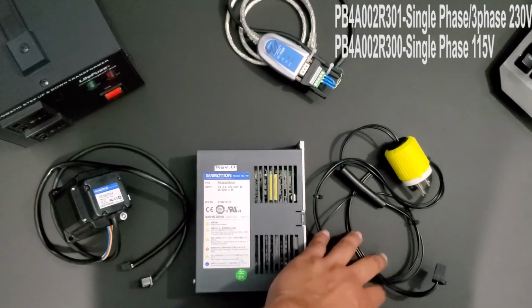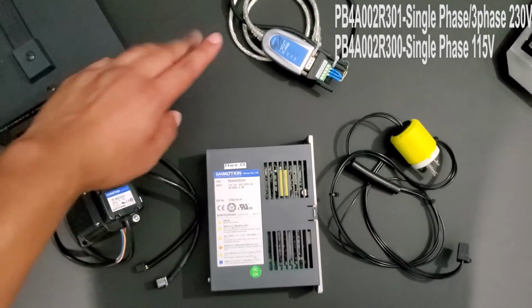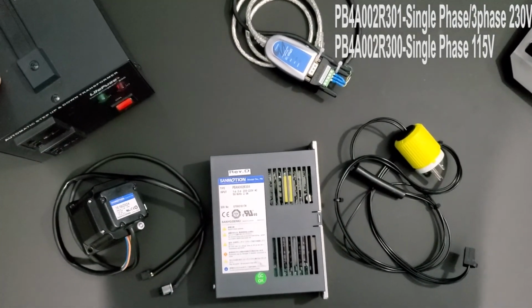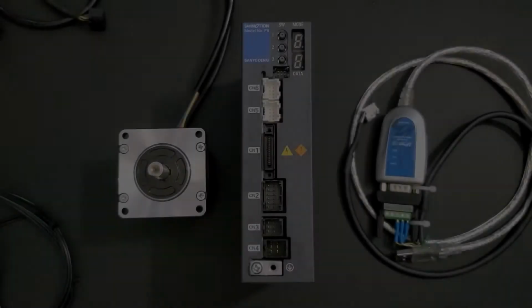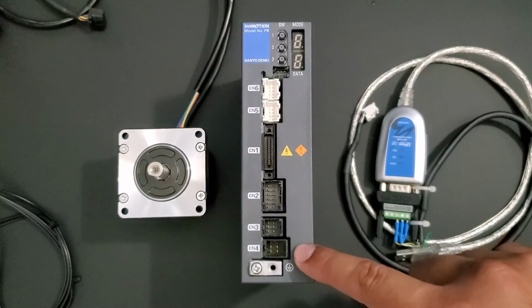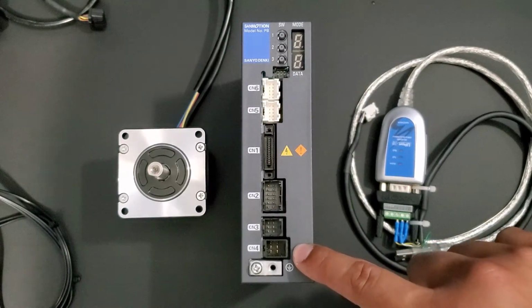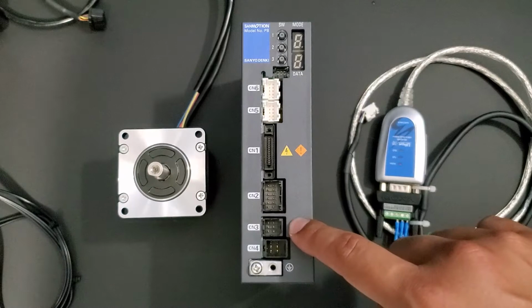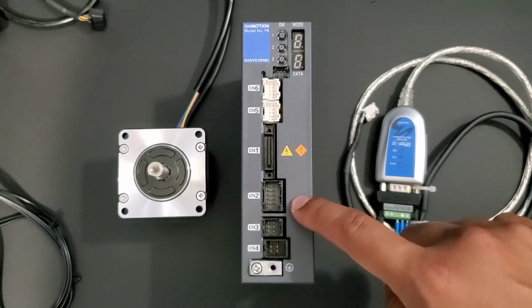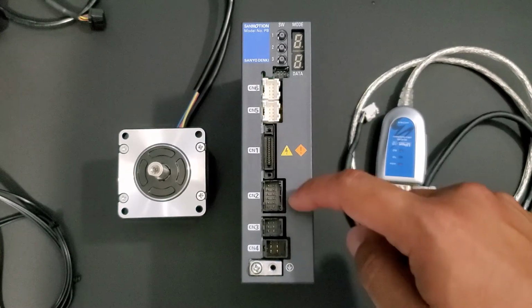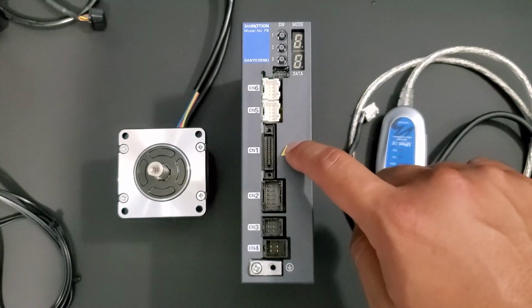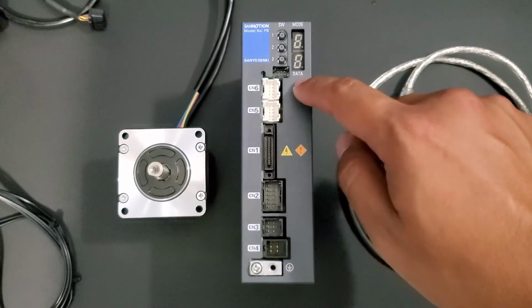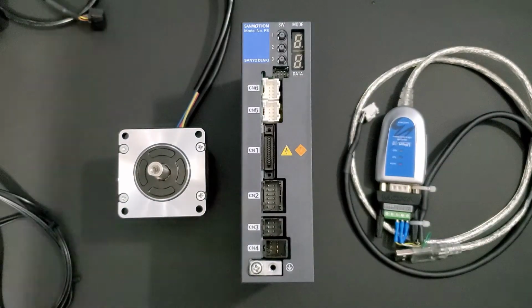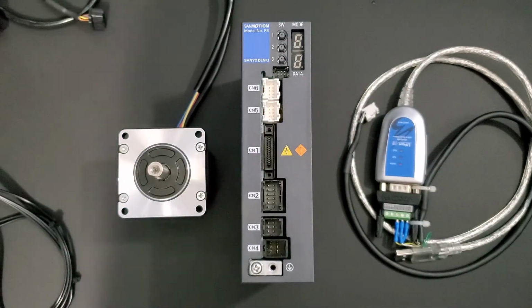I have the main input power connector and I have a Moxa USB to serial adapter. CN4 is for your main input power, either single phase or three phase. CN3 is for your motor power connector. CN2 is for your motor encoder connector. CN1 is for your input and output. CN5 and CN6 is for your communication cable and/or if you daisy chain this drive.